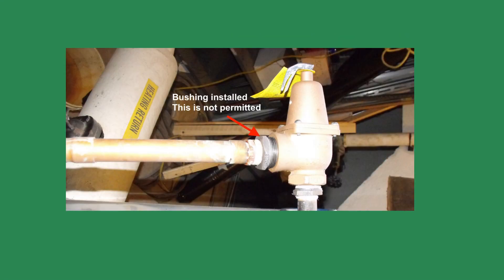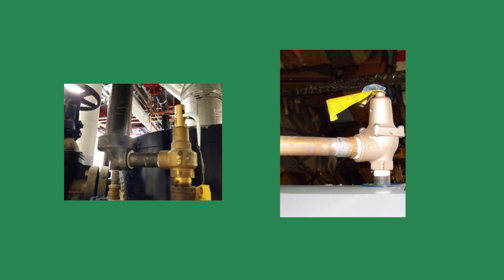The following is a list of common mistakes with boiler safety relief valve installations. Relief valve piping. The relief valve discharge piping cannot be reduced. See International Mechanical Code 1006.6. By reducing the discharge pipe size, the relieving capacity of the safety valve is lowered and may not be able to safely relieve the pressure inside the boiler, causing a dangerous situation. The code also states the discharge material shall be of rigid pipe approved for the system's temperature. The inlet pipe size shall be the full diameter of the pipe inlet for the relief valve.